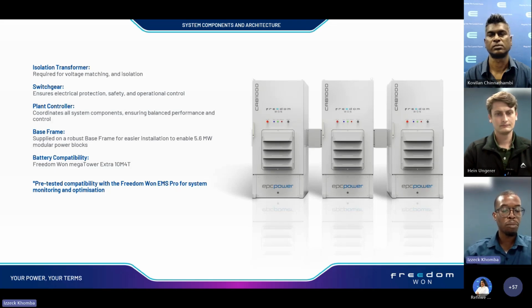Then the base frame is mostly required for skid application, whereby the integrated inverters in a cluster can be connected via throat connection to a transformer. Those clusters can be positioned anywhere and integrated together to form a large microgrid plant or application. Then the battery compatibility: the inverter is compatible with our Mega Tower Extra. You need a minimum of 2 batteries for a single inverter to get the full 1.4 inverting capacity. So depending on your energy storage requirement, you can scale the inverters. You can connect more batteries on one inverter, but the minimum requirement to get the full inverting capacity is 2 Mega Tower Extras.